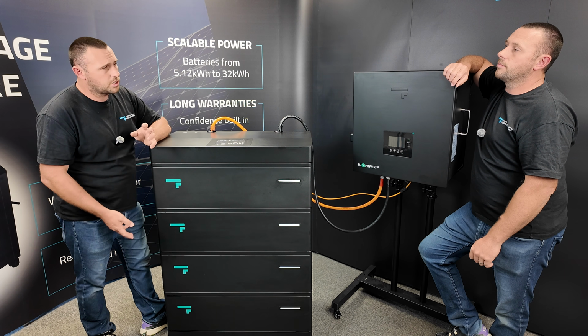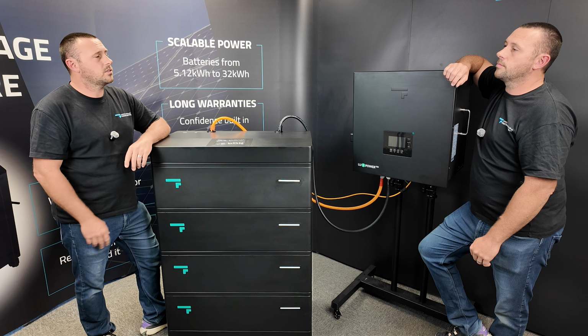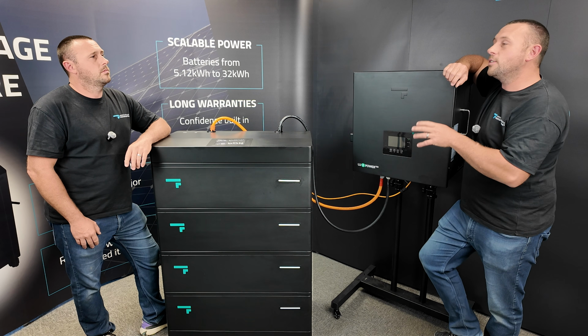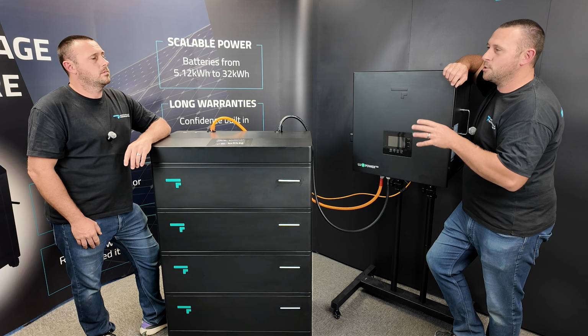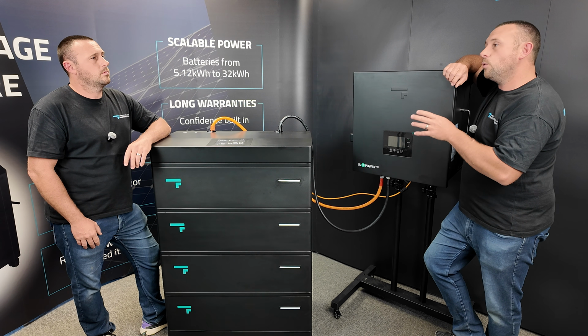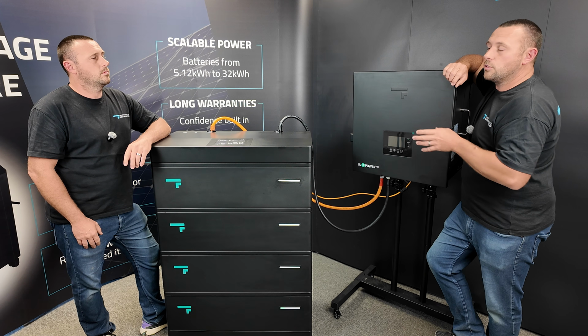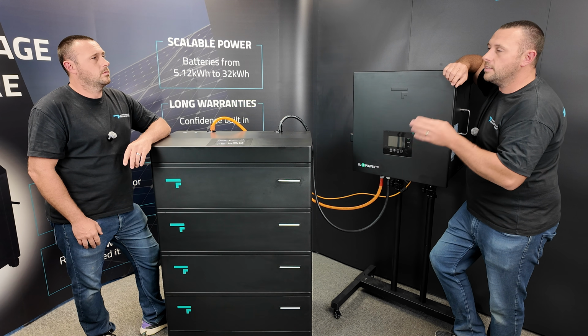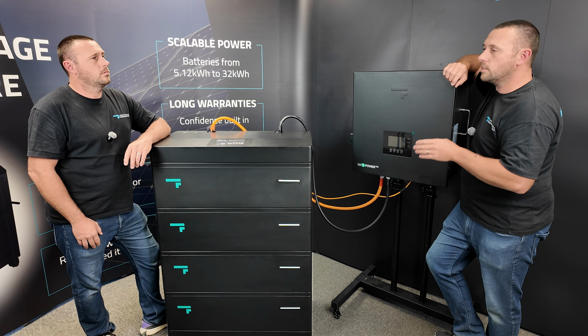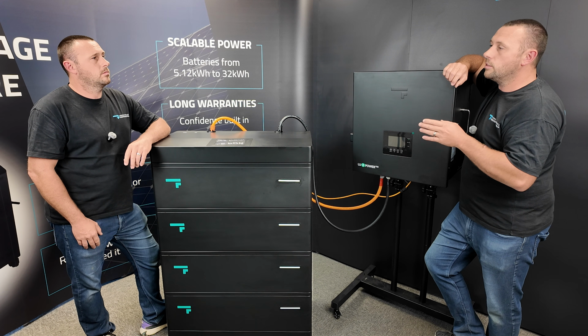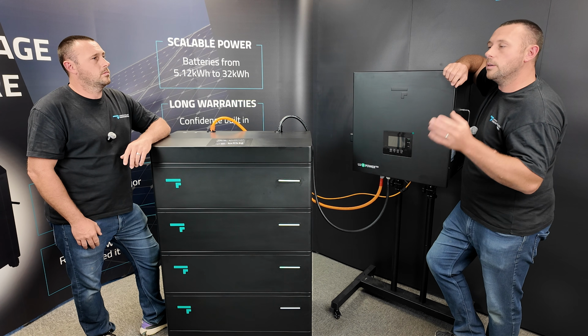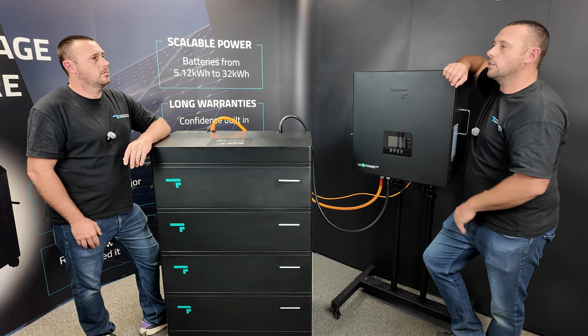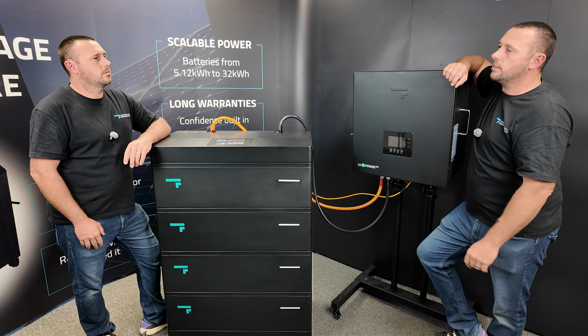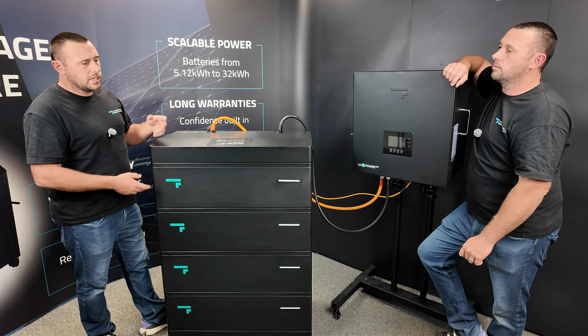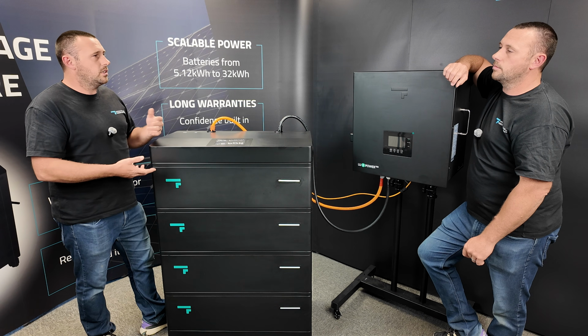So what's the temperature range of the battery? Is there specifics for that? The battery is designed to operate in the worst of the English weather, so it'll handle up to 45 degrees and down to -20. The battery is equipped with cell heating, which is automatic and triggers at 0 degrees. Anything below 0, it will start to heat the cells before it starts to charge them, just to make sure nothing gets damaged.